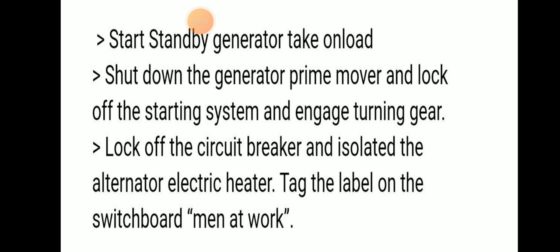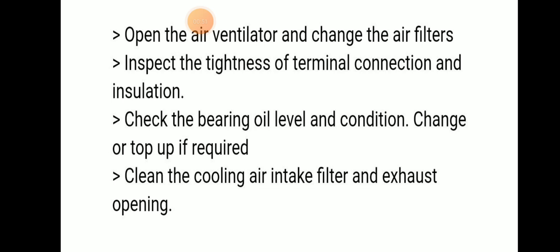And first, like I mentioned, we have to start the standby generator and take it on load, then shut down the generator and prime mover, lock off the starting system and engage the turning gear. After that the circuit breaker should be locked off and isolated. Then we have to place the placard, men at work board. Then after this we have to open the air ventilator and change the air filter.